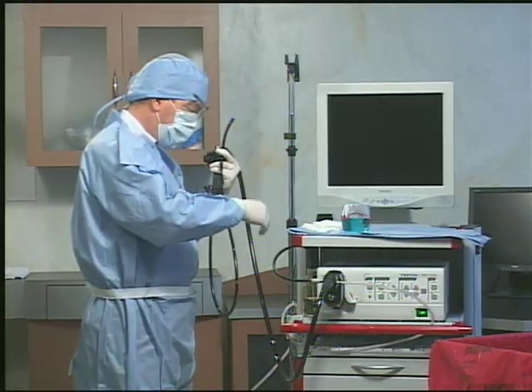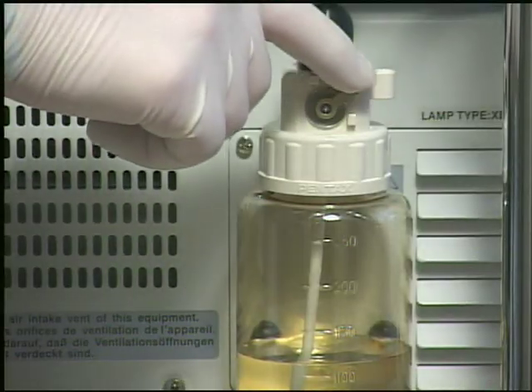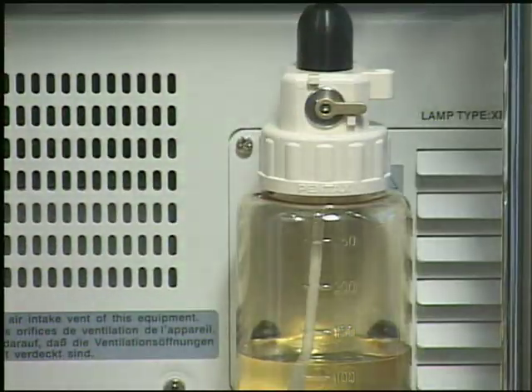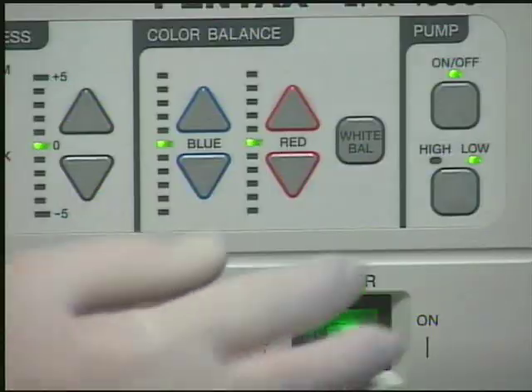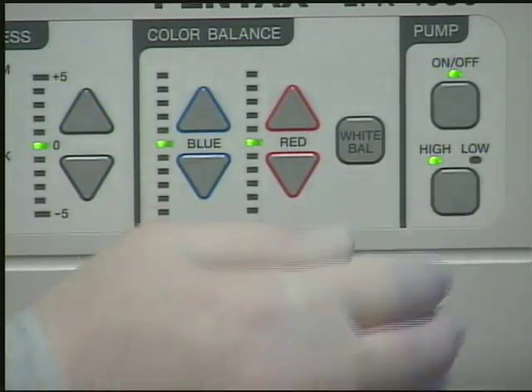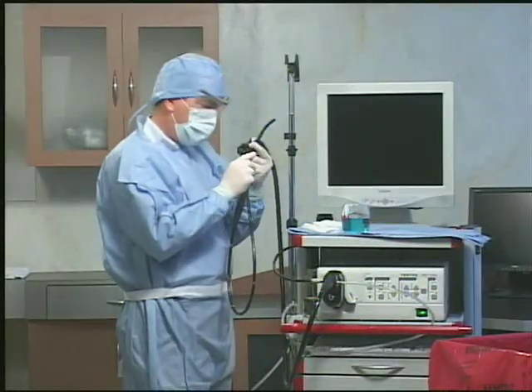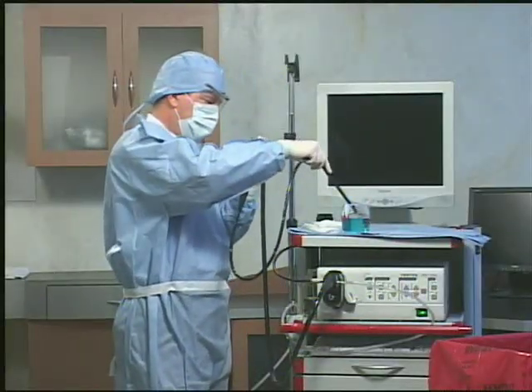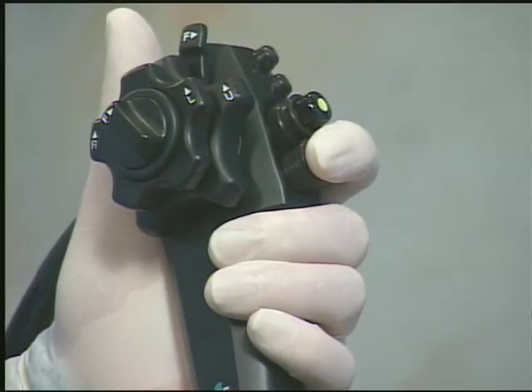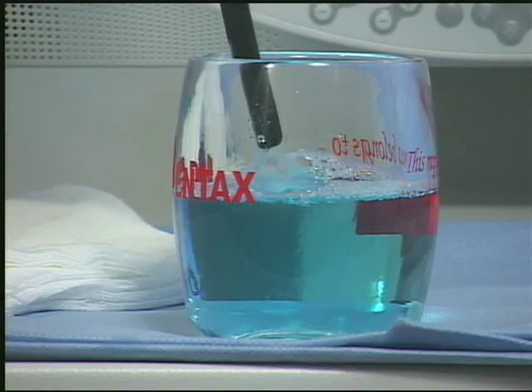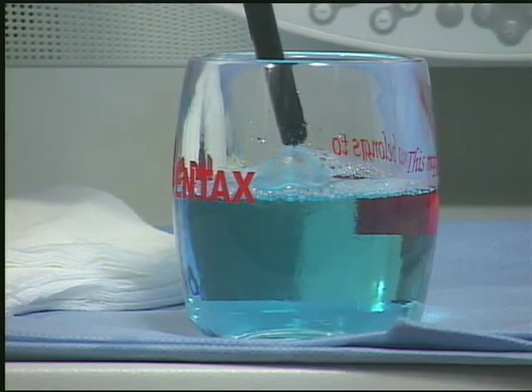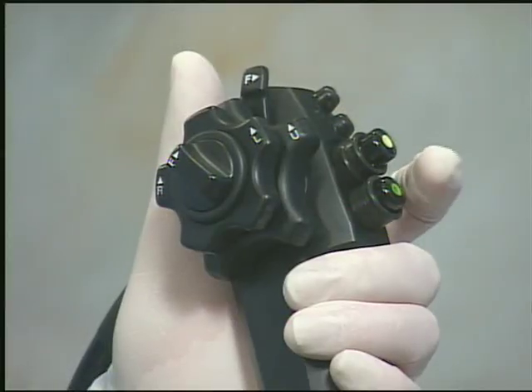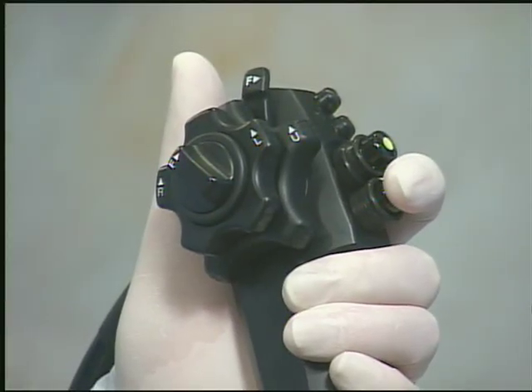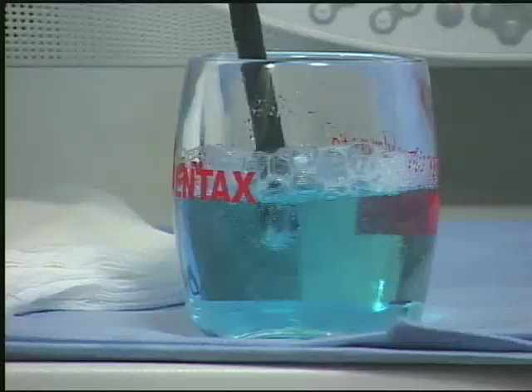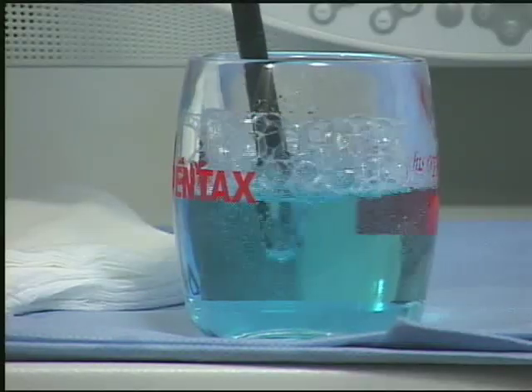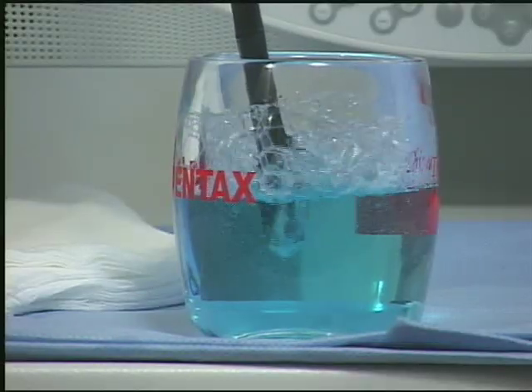Set the lever on the water bottle to the drain position. With the air pump of the video processor on and set to the highest pressure setting, depress the air-water valve of the scope fully until all water has been discharged from the scope. Alternate covering the hole in the valve and depress the valve to forcefully expel mucus, debris, etc., which may have entered the air and water nozzles.